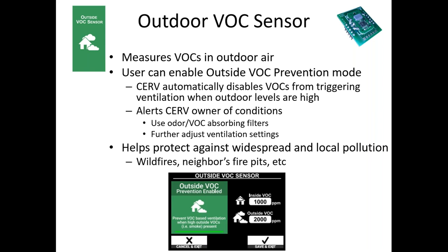So this can automatically disable VOCs from triggering ventilation, so then you won't get into that kind of situation. It'll also notify the user that this operation is going on, so you can make further adjustments to the ventilation setting and control, or you may then use a specific filter, an odor VOC absorbing filter, a carbon filter, during these times to help take those pollutants out.